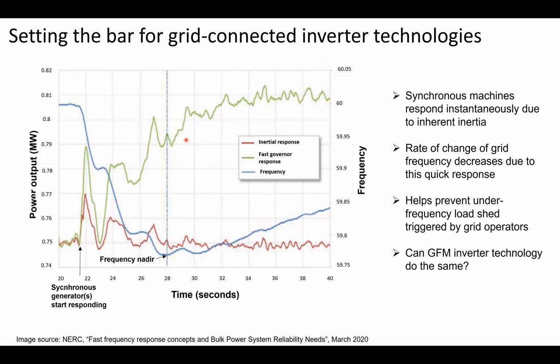Okay, so I included this slide, it's from NERC, just to set the stage for what grid-connected inverter technologies should have in terms of capabilities. Similar to what Cameron was saying, having a fast frequency response is crucial for many reasons, but one reason here is that it helps slow down the df/dt if you have a faster, quicker response. As everyone knows, synchronous generators have an inertial response. You can amplify it through a fast governor response. Another benefit to having a faster response is you can prevent some of the oscillations that could be possible in a low inertia grid, like KIUC's with more renewables.